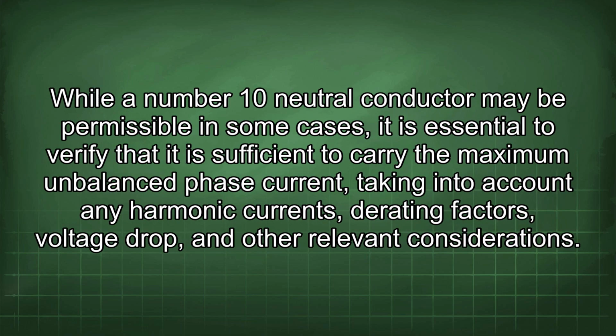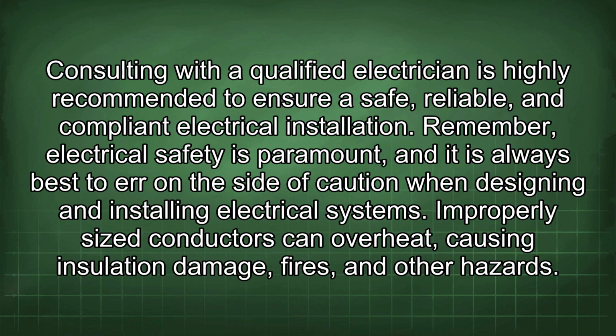While a number 10 neutral conductor may be permissible in some cases, it is essential to verify that it is sufficient to carry the maximum unbalanced phase current, taking into account any harmonic currents, derating factors, voltage drop, and other relevant considerations. Consulting with a qualified electrician is highly recommended to ensure a safe, reliable, and compliant electrical installation.